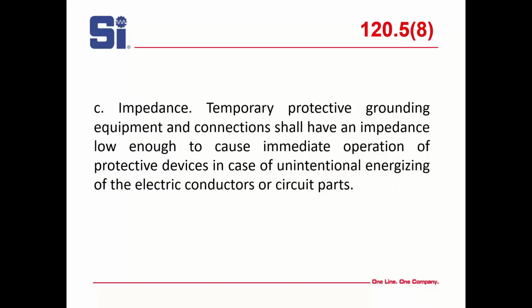Temporary protective grounding equipment and connections shall have an impedance low enough to cause immediate operation of protective devices in the case of unintentional energizing. And if you do not have proper size grounds, they're going to fuse, which means they're going to melt. Then you don't have to worry about impedance because everybody's dead.